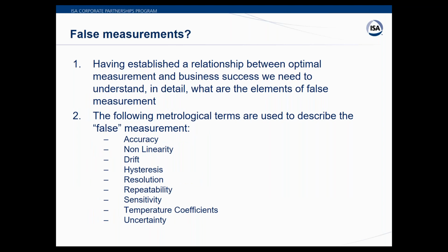So we've looked at the measurement side, and we've talked about how we break it down. If we go back to the earlier statements I made about being optimized on what you're doing, we need to be aware that there are always things that can trip us up. Everybody focuses on accuracy, and we're going to talk about that today. But in addition to the base accuracy of an instrument or a calibrator, there are other factors that maybe aren't as significant but need to be considered. How linear is the device? Does it have hysteresis? Does it have some other phenomenon that you need to analyze? How much does the instrument drift over time? Does it drift significantly in a six-month window, a one-year window?